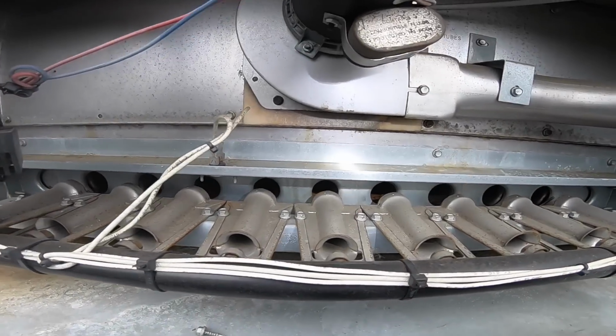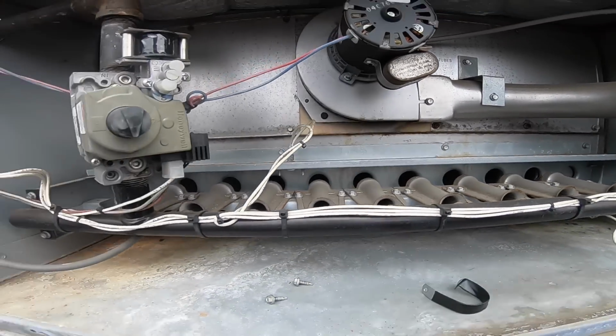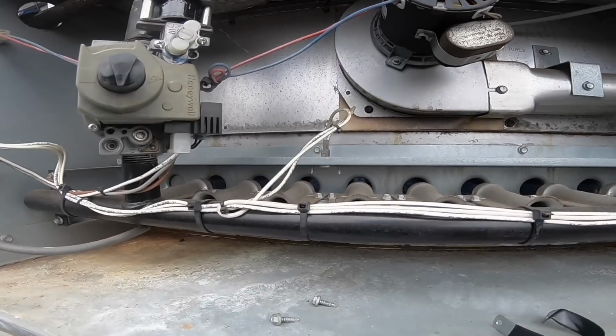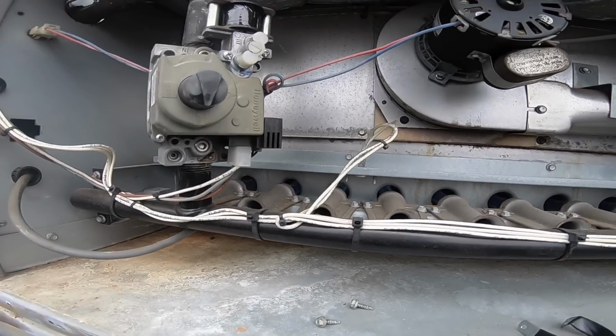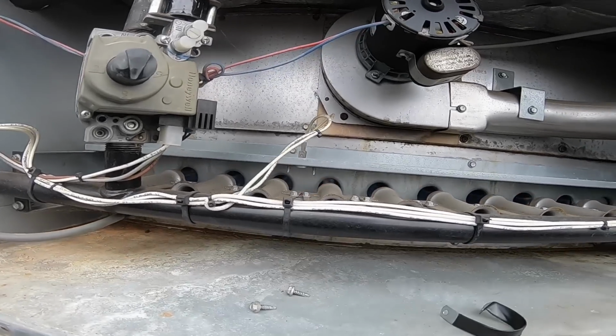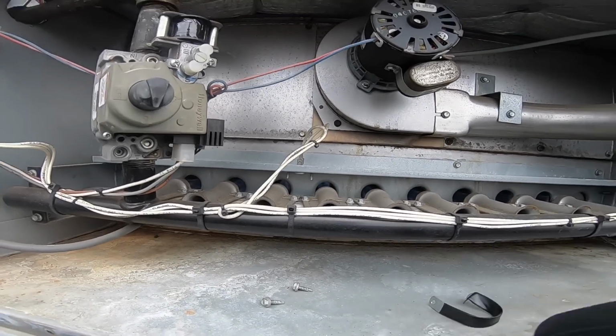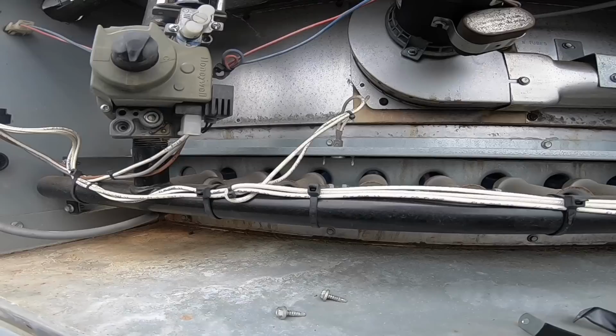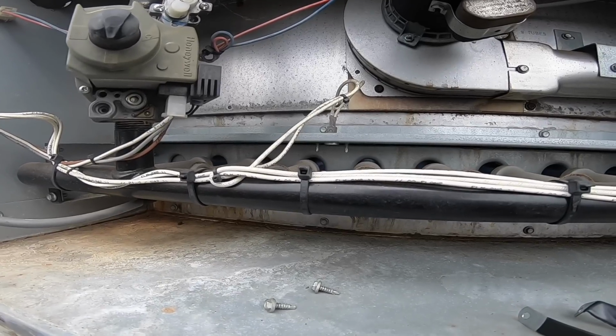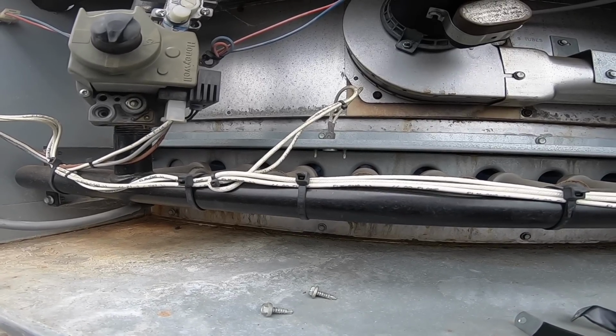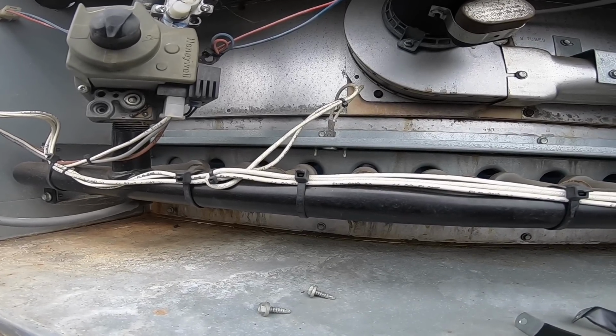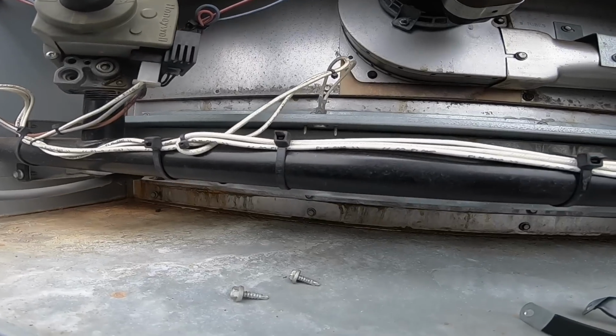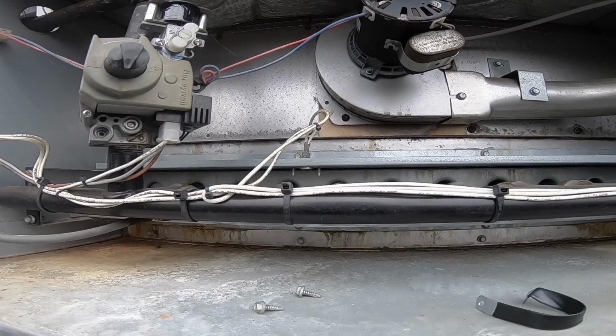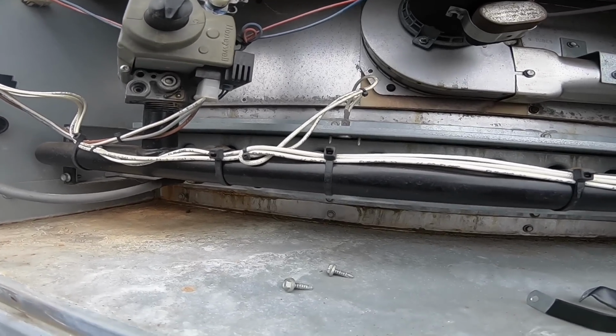There's a lot of rust and gunk in those burners. There goes the fire, I think the second tube and one of these, but blower's not on yet. I have to do an amp draw on that motor, it's got a little noise to it.